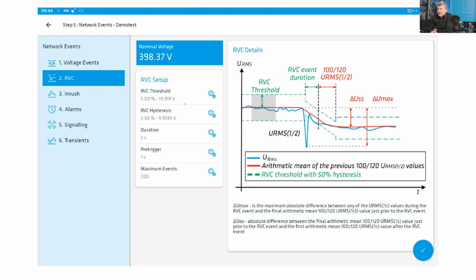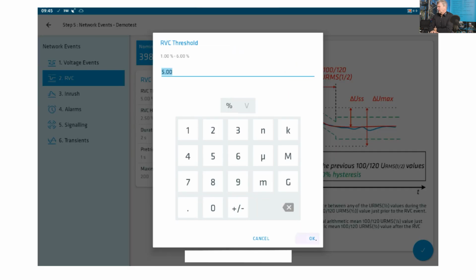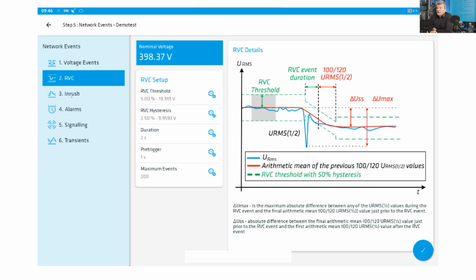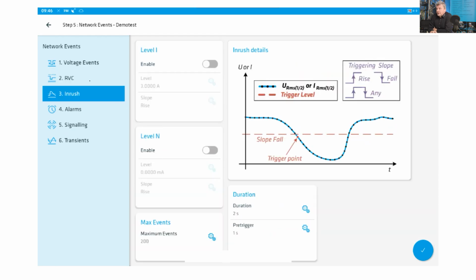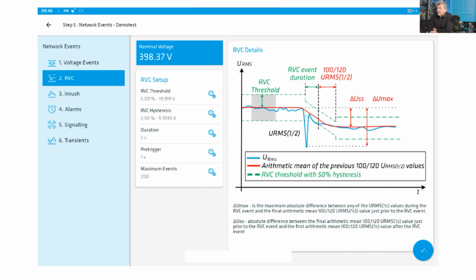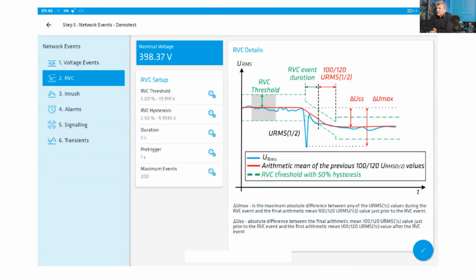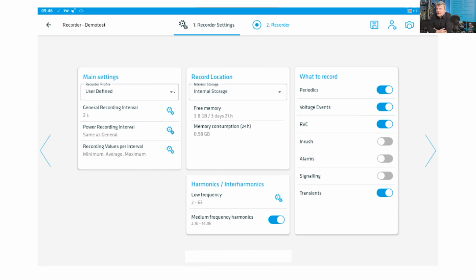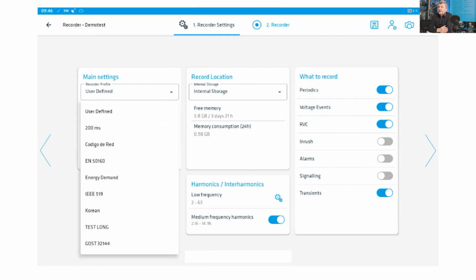Normally for the voltage events, RVC, you have the setup according to the standard. You can change voltage events, RVC, and other network events, which are defined by default according to the standard. You can change them if you want, but if you're satisfied, you can use them as they are. Just confirm this and continue, and it will automatically drive you to the recorder screen, where you can define which recorder profile you will use.